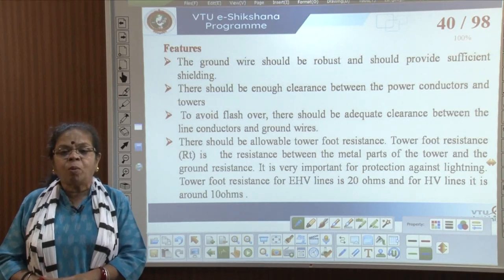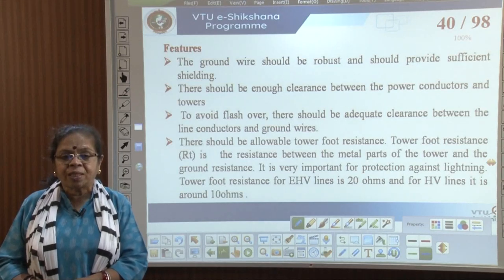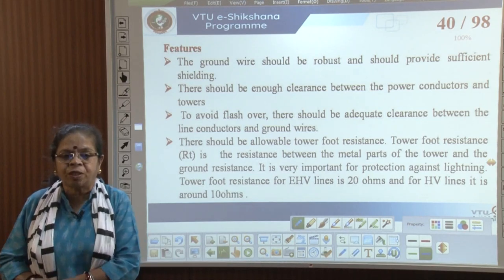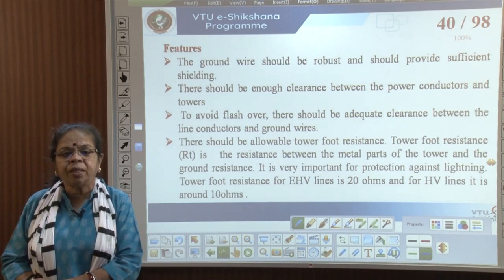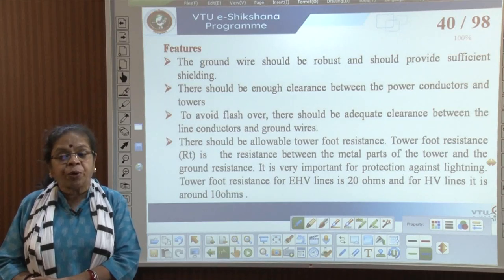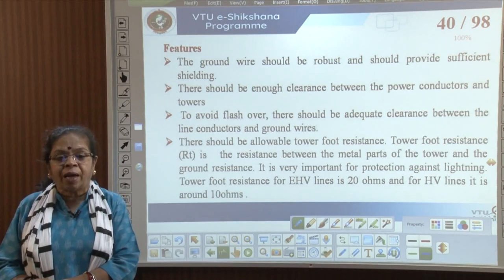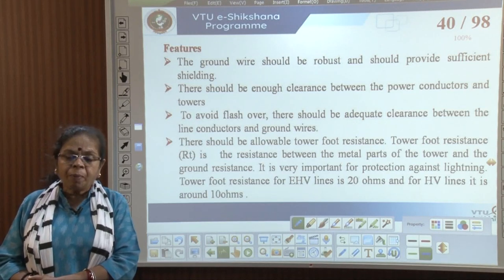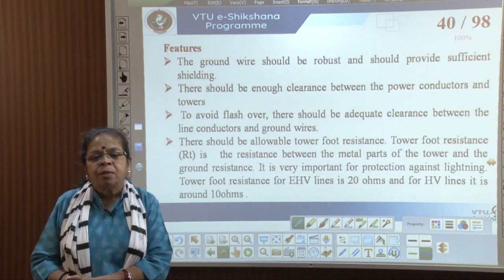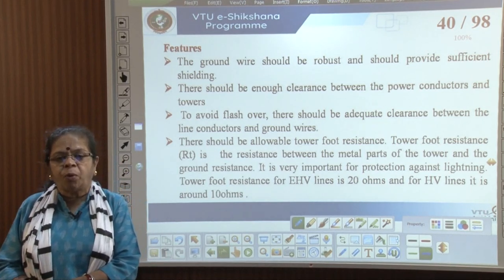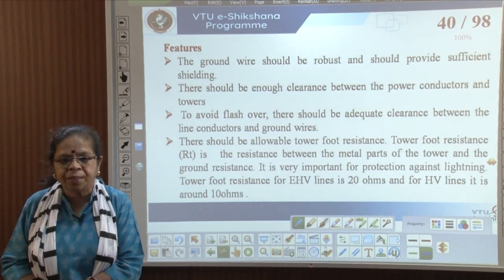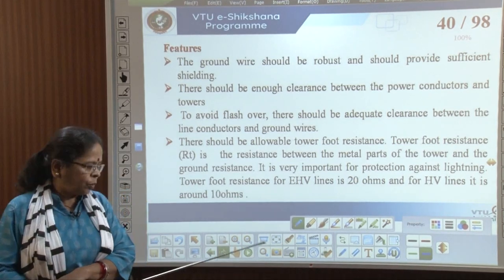There should also be allowable tower foot resistance — the resistance between the metal parts of the tower and the ground. This is very important for protection against lightning. For EHV lines, the tower foot resistance is around 20 ohms, and for HV lines it is around 8 to 10 ohms.